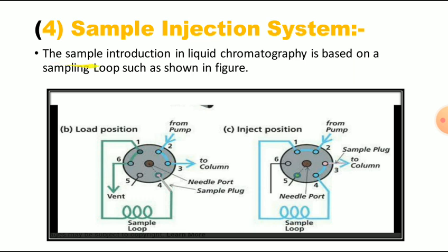The sample introduction in liquid chromatography is based on a sampling loop, such as shown in the figure. So see the figure, this one. This is actually the load position. That means in this load position we can load the sample into the system. This is the injection position. That means injection of this sample into the column, that we are going to see now.